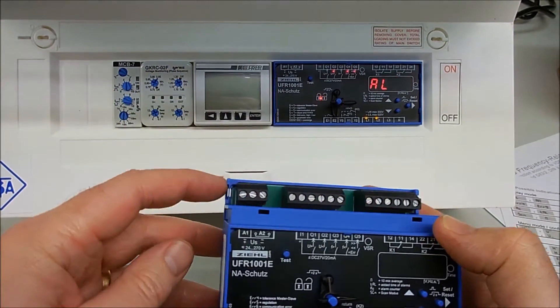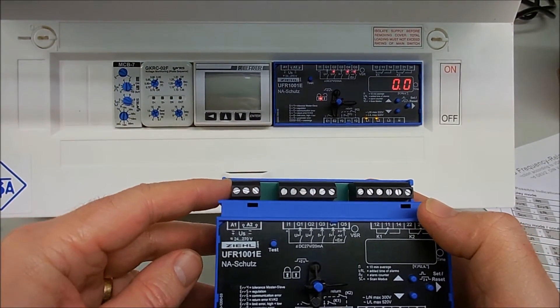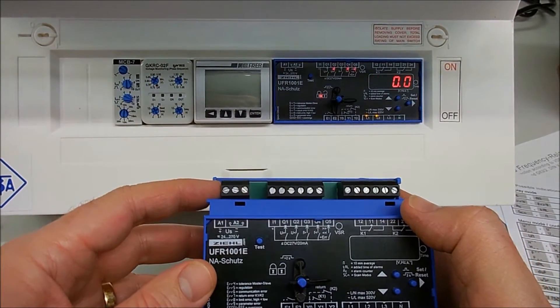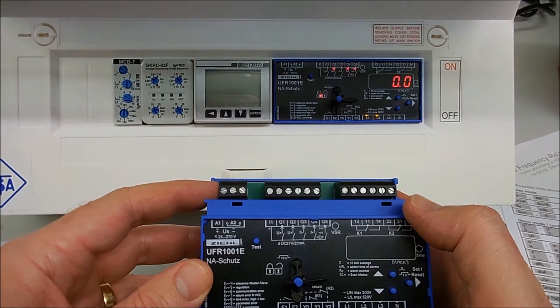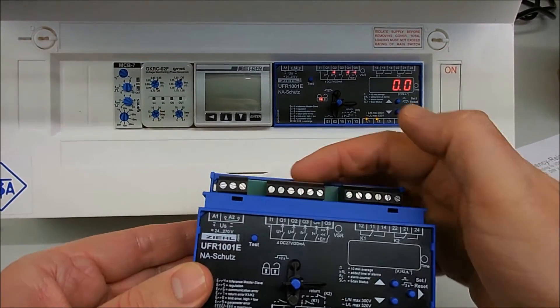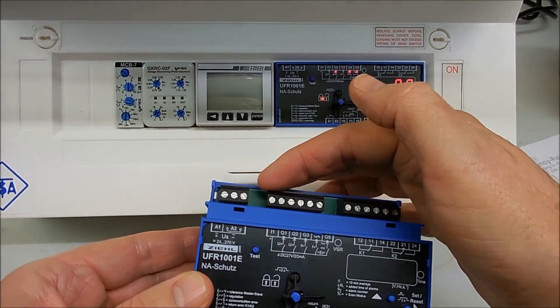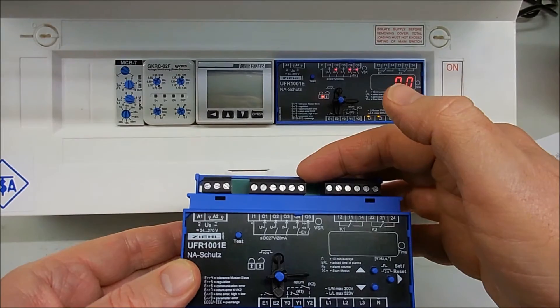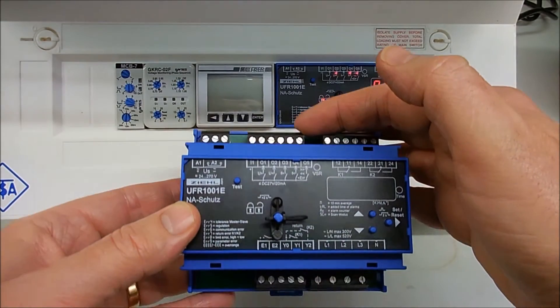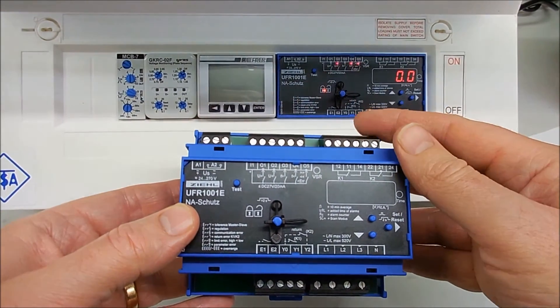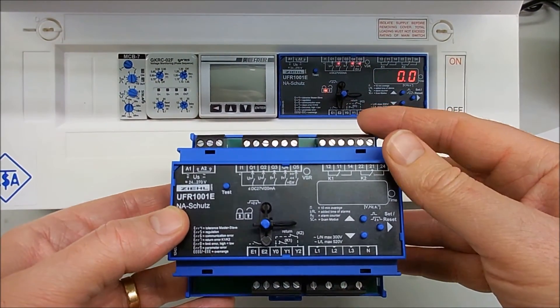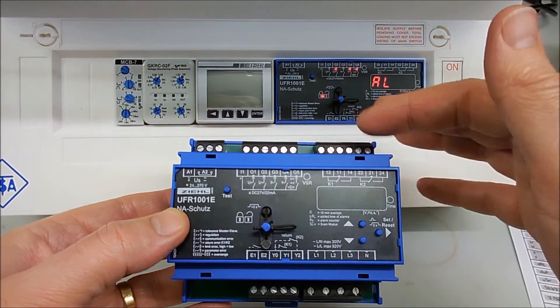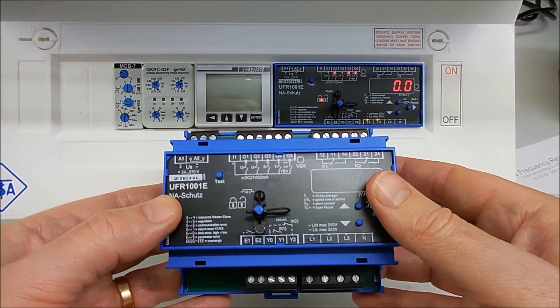You have the mains connection up here which is from 24 to 270 volts AC DC. You have digital outputs here for each of the values being monitored. That requires an external power supply if you want to use that. And you have the relay outputs here to your mains and generator breaker.